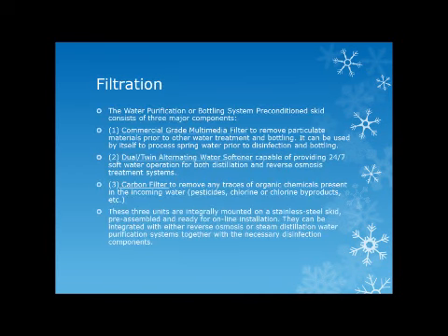The water filtration system. The water purification or bottling system preconditioned skid consists of 3 major components. Number 1, a commercial-grade multimedia filter to remove particulate materials prior to other water treatment and bottling. It can be used by itself to process spring water prior to disinfection and bottling. 2, a dual/twin alternating water softener, capable of providing 24/7 soft water operation for both distillation and reverse osmosis treatment systems.